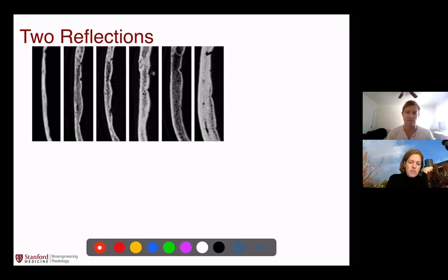So if you look at some of these, you see the outer surface is nice and flat. You can get your transducer right up against it, nice and flat, and be relatively assured you're going to have pretty reasonable normal incidence. But then you can see on the other side that there's all those variations. And so if you have normal incidence here, you may not have normal incidence in other locations and other parts of the skull. So it can be very, very complicated.